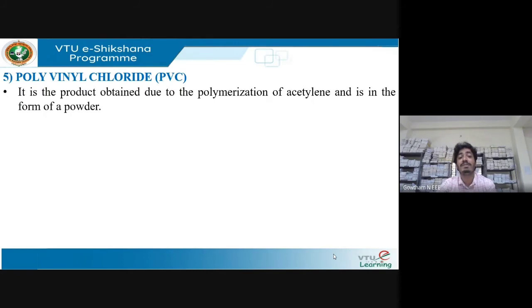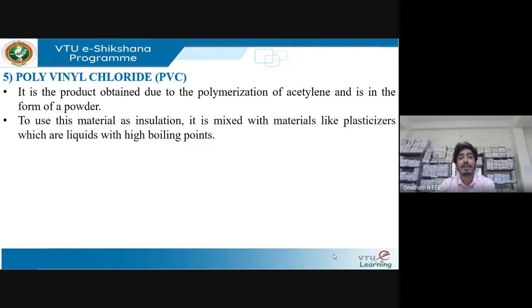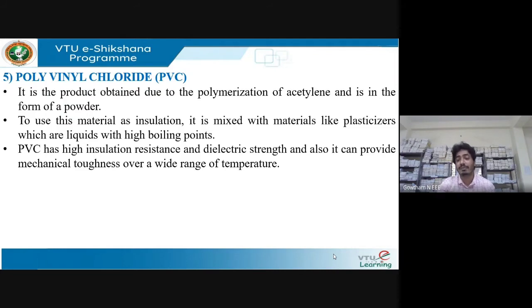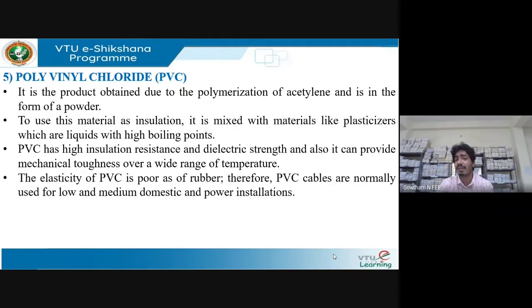PVC — polyvinyl chloride — is formed by polymerization of acetylene. It is an organic compound in powder form. When used as an insulator, it is mixed with plasticizers, which are liquids with high boiling points. PVC has high insulation resistance, high dielectric strength, and can provide mechanical toughness over a wide range of temperatures. Its elasticity is poor compared to rubber. It is used for low, medium, domestic, and power insulation applications.